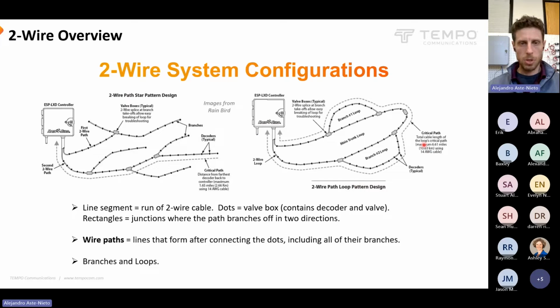Certain systems, when you loop things, the loop can start at a controller and then end all the way back in the same controller in a different port. Some systems don't allow that. You can still do loops, but those loops can't come all the way back to the controller. They might have to end early.